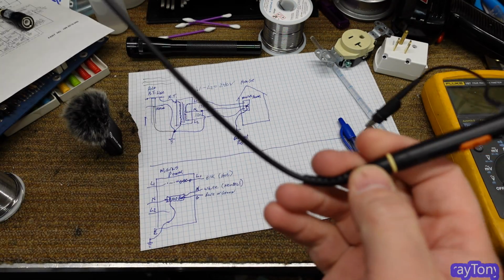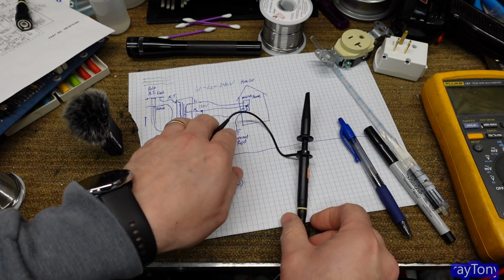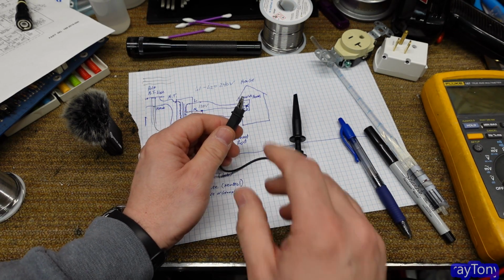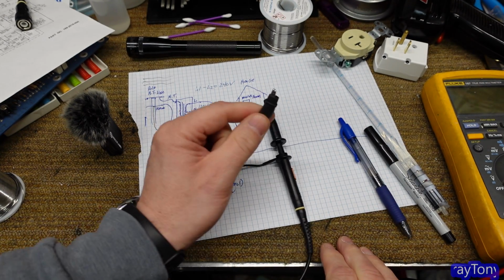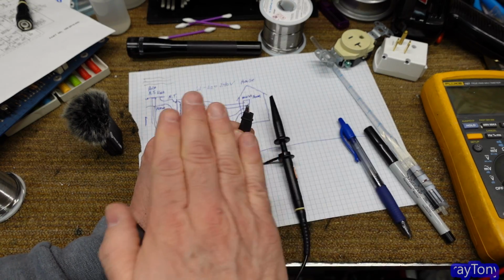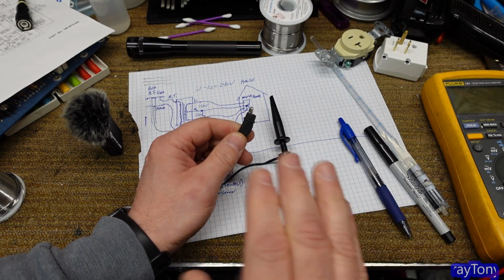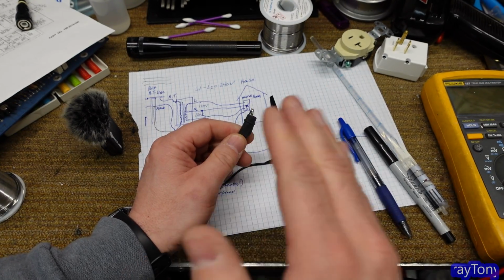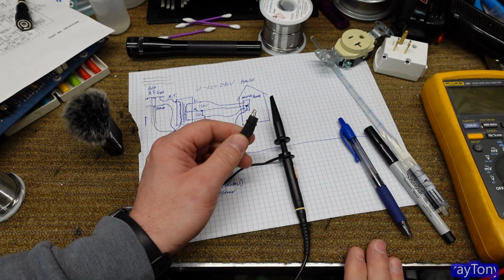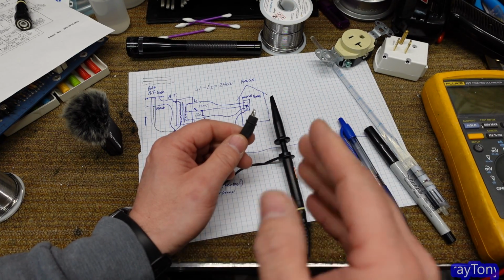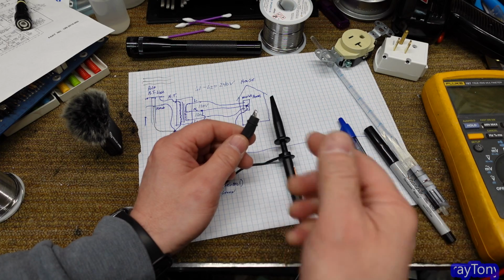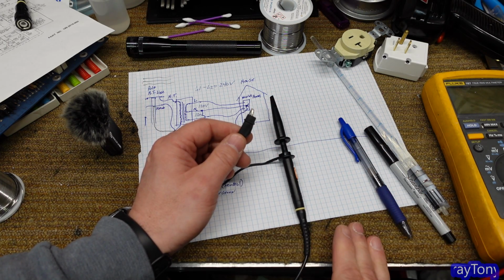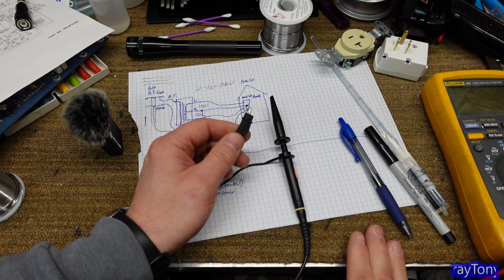So here's where the problem comes in. If I connect this terminal of my probe to anything that is not earth ground, anything that is a different voltage than earth ground, I am now connecting that voltage directly to earth ground, causing a short.